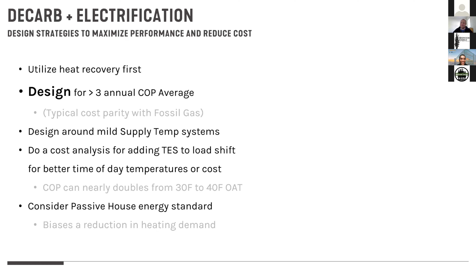My last plea for all the regulatory folks on board, I'm hoping there's some CEC folks here: consider implementing the Passive House Energy Standard. Even in California, nobody is talking about the benefits of right-sizing a heat pump when your building enclosure is biasing you against heating. Everything in our standard right now is based on TDV and cost effectiveness, but nobody's talking about purchasing the equipment. If I designed the Passive House Building Standard, even in a commercial building, I can almost guarantee your heat pump size will be about half of what it is if you follow current code. So that's my plea to the world: be better designers, be smarter designers, and actually design around real equipment.